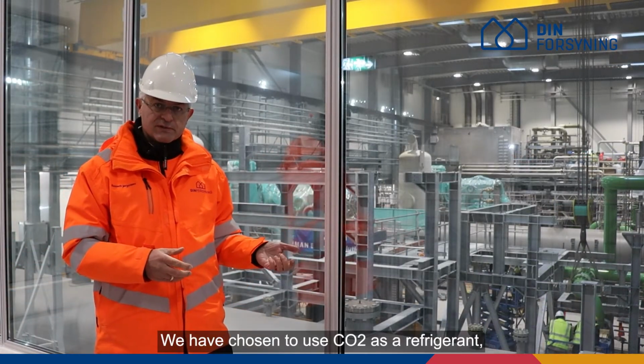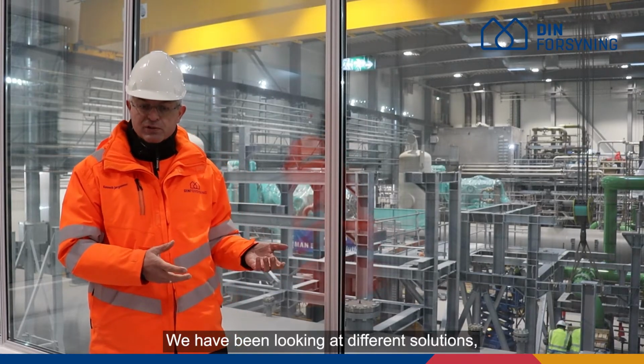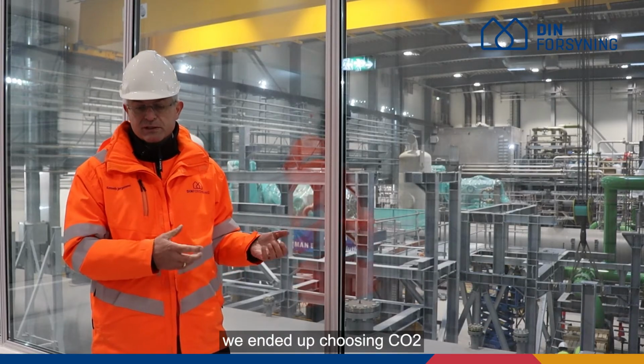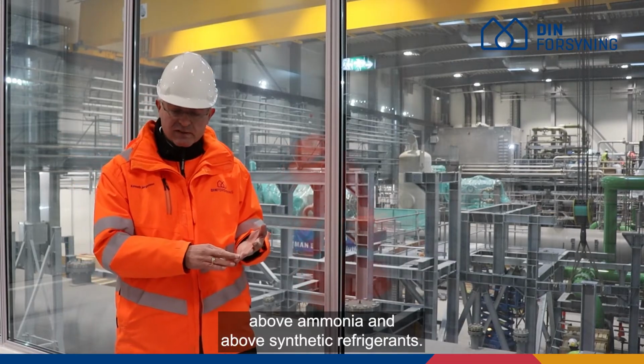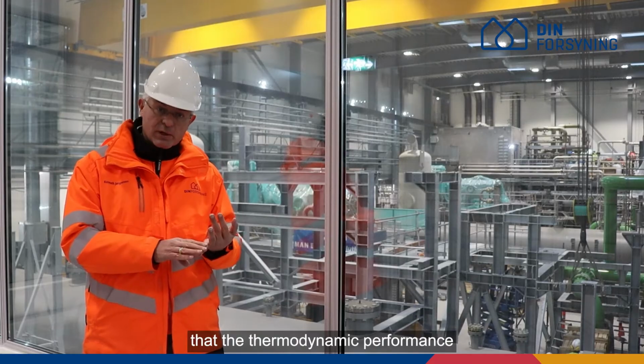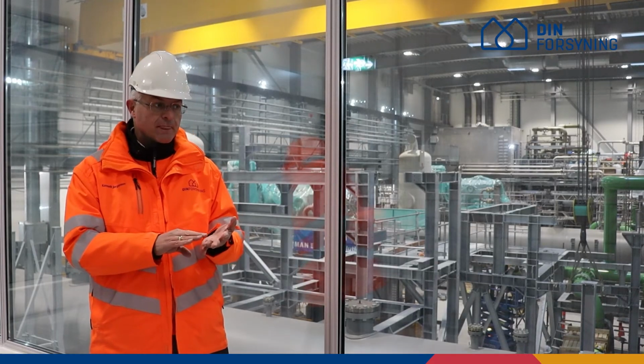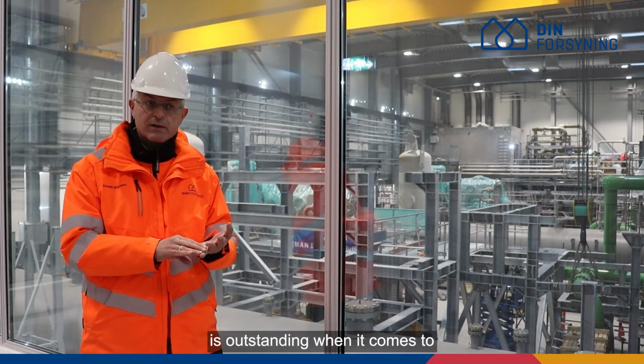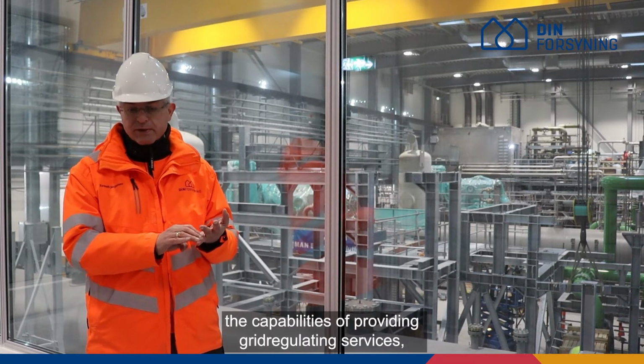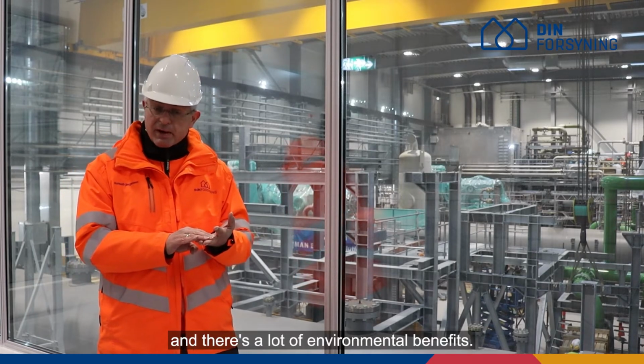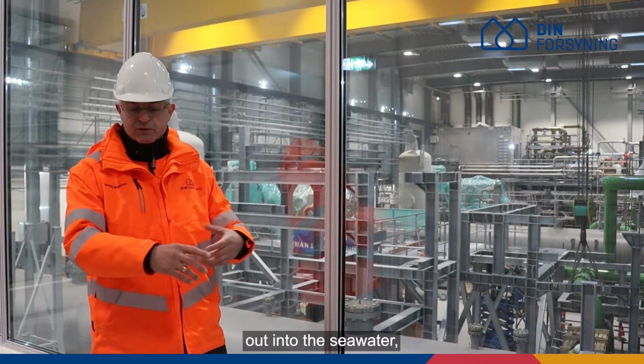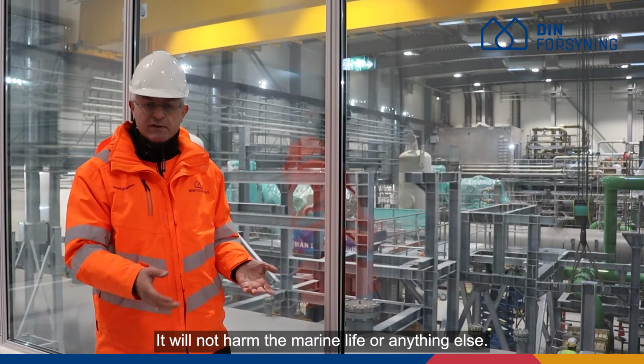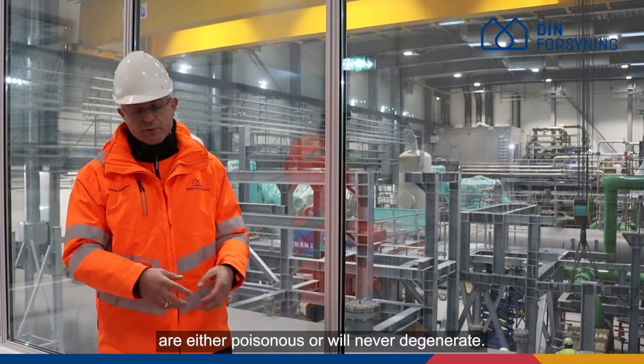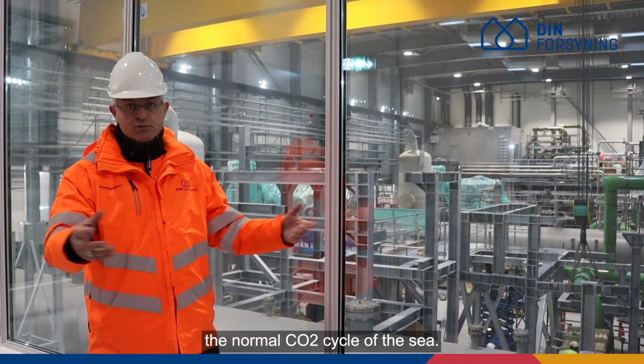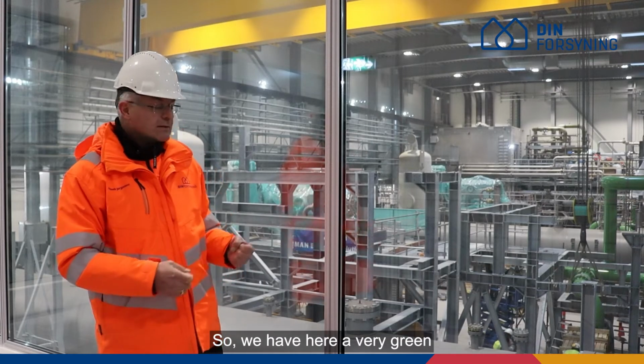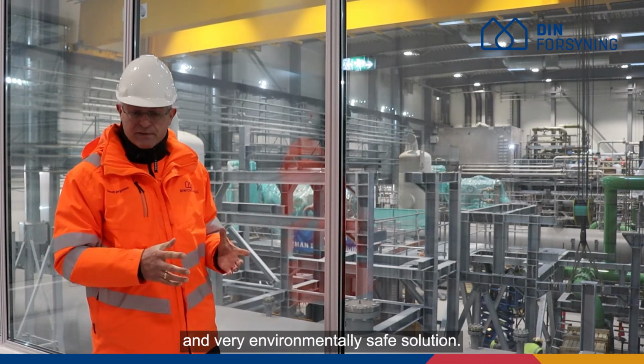We have chosen to use CO2 as a refrigerant because it's environmentally friendly. We have been looking at different solutions, but in our final decision, we ended up choosing CO2 above ammonia, above synthetic refrigerants. The reason for that is that the thermodynamic performance is just as good as the other refrigerants. The performance here, especially on the compressor, is outstanding when it comes to the capabilities of providing grid regulating services. And there are a lot of environmental benefits. If CO2 leaks into the system, out into the seawater, it's completely harmless. It will not harm the marine life or anything else. Whereas other refrigerants are either poisonous or will never degrade. The CO2 will basically just enter the normal CO2 cycle of the sea. So we have here a very green and very environmentally safe solution.